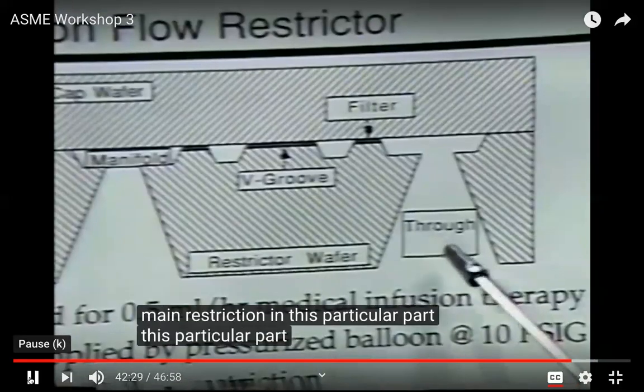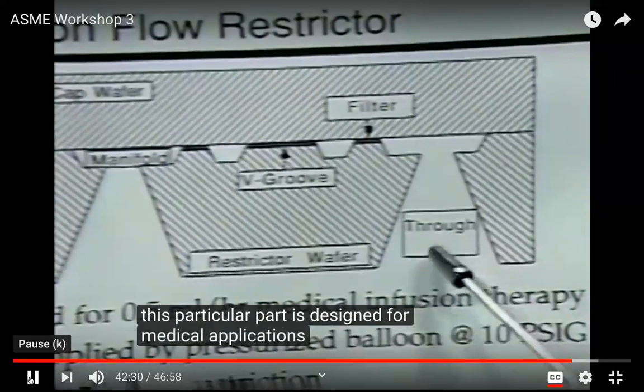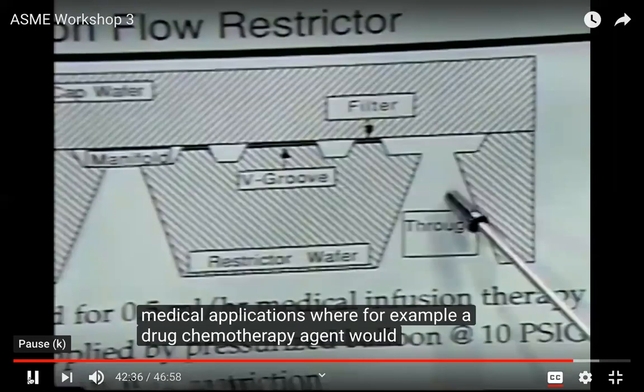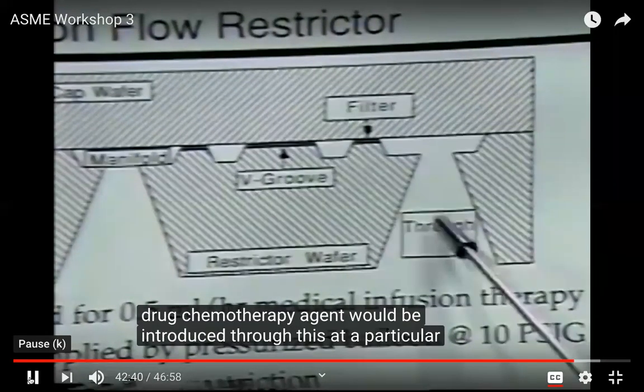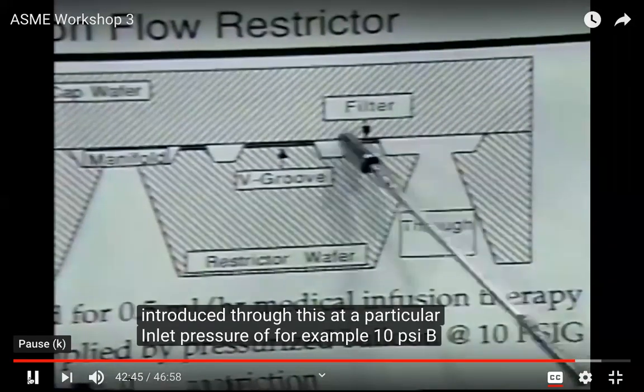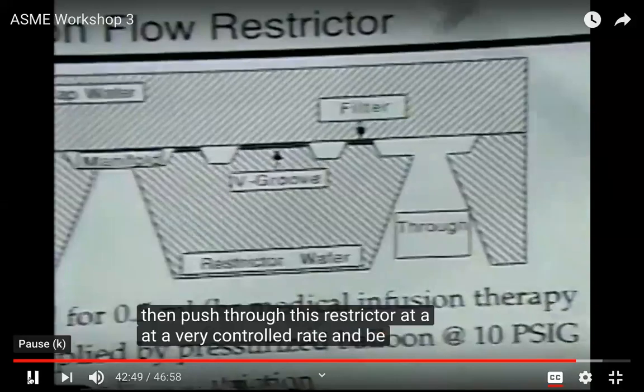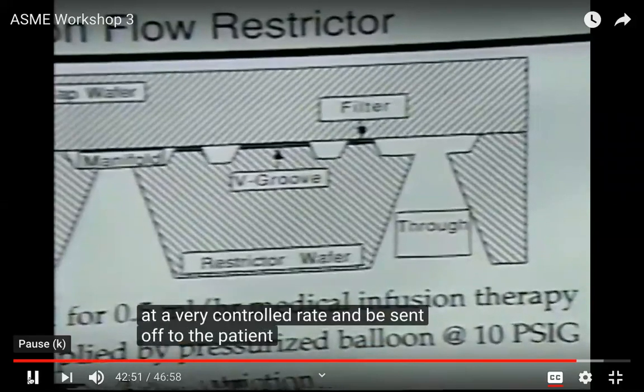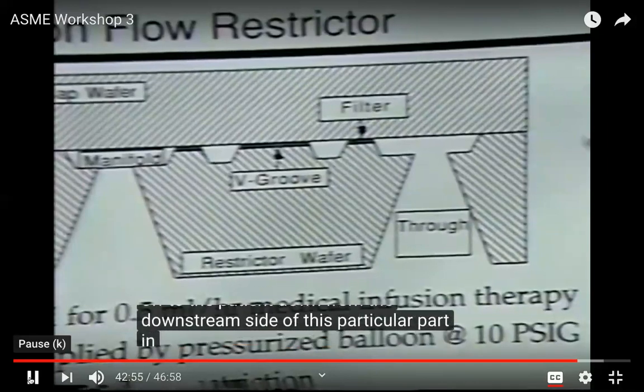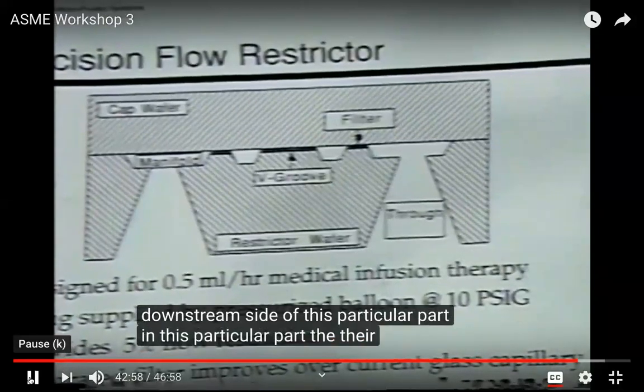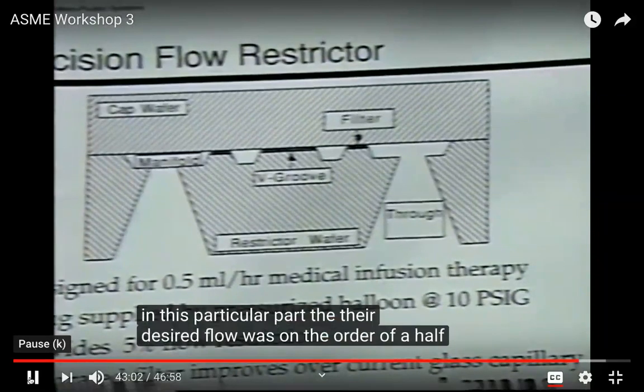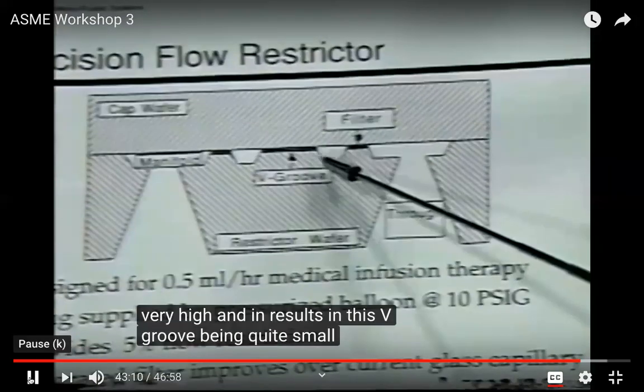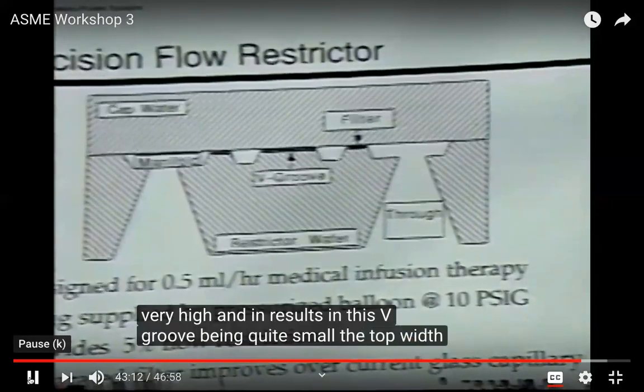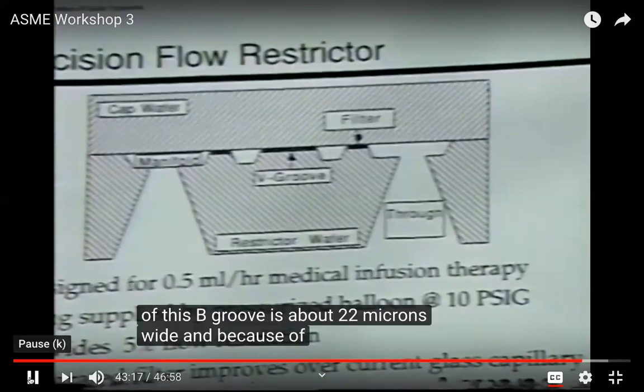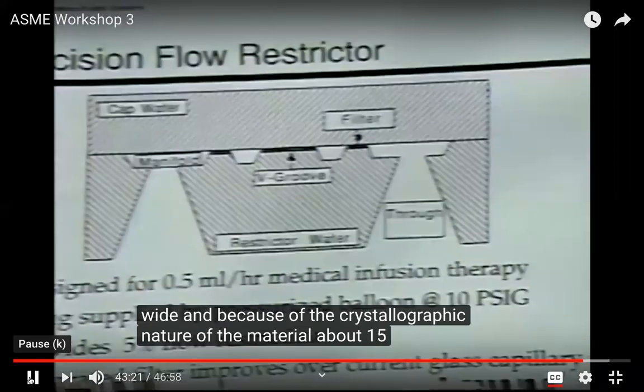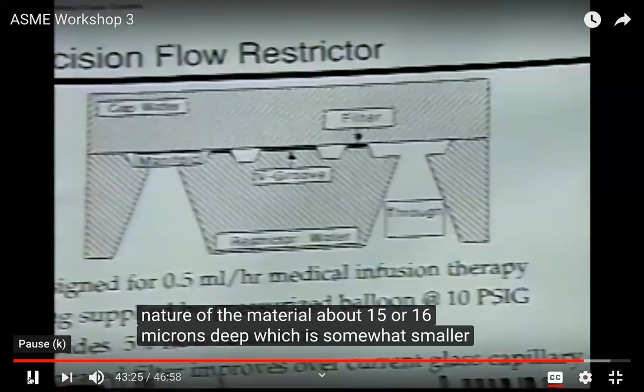This particular part is designed for medical applications where, for example, a drug, chemotherapy agent would be introduced through this at a particular inlet pressure of, for example, 10 psi, be then pushed through this restrictor at a very controlled rate and be sent off to the patient from the downstream side of this particular part. In this particular part, their desired flow was on the order of half a ml per hour, which is really not very high and results in this V groove being quite small. The top width of this V groove is about 22 microns wide, and because of the crystallographic nature of the material, about 15 or 16 microns deep, which is somewhat smaller than the proverbial human hair.